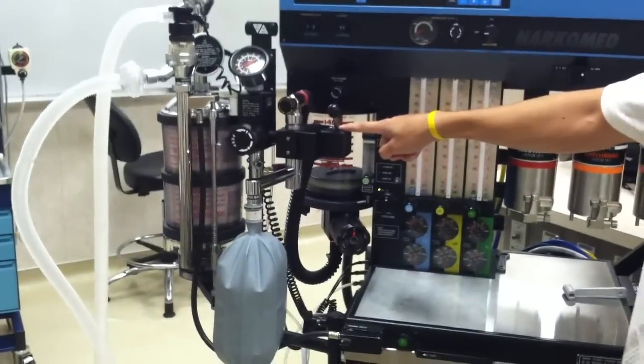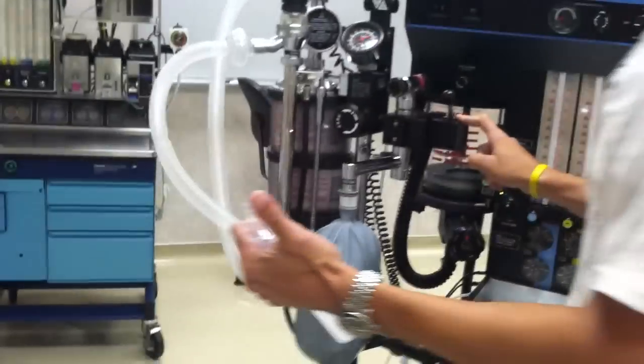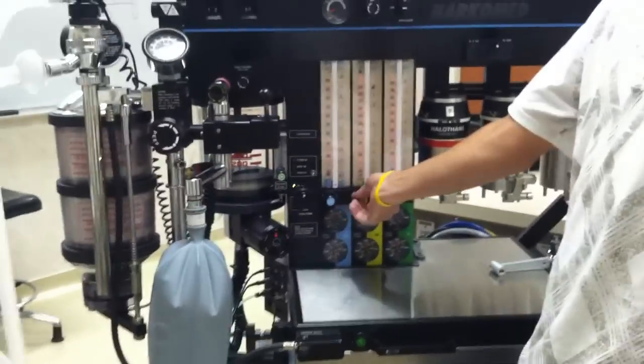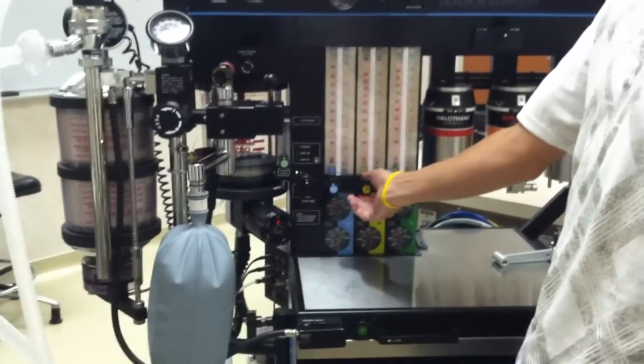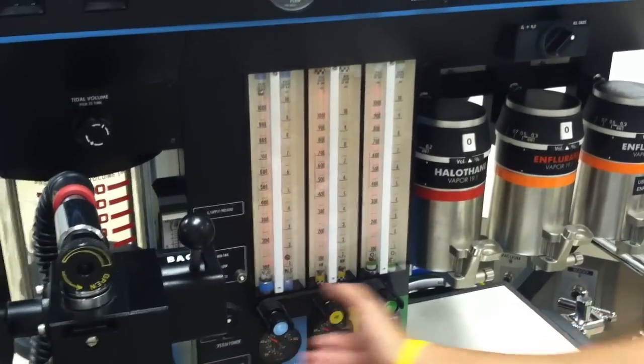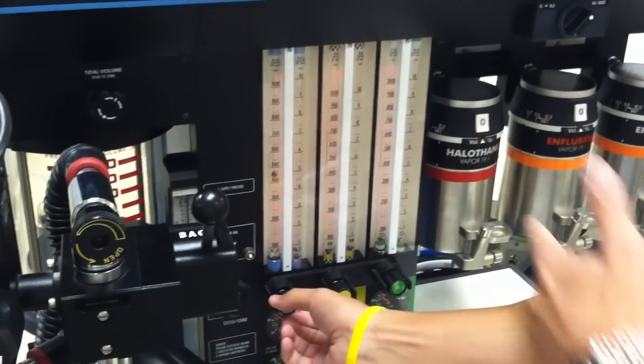On this machine, we want to make sure that this knob is flipped to all gases. We want to make sure that the machine is in bag mode, which it is. We're going to go ahead and take this. It's a bag mode, but first, like the other one, we want to go ahead and check our flow meters. So we're going to take our air first, go all the way up. Special note on this machine, as you notice, you can't turn on the nitrous without the oxygen being on.